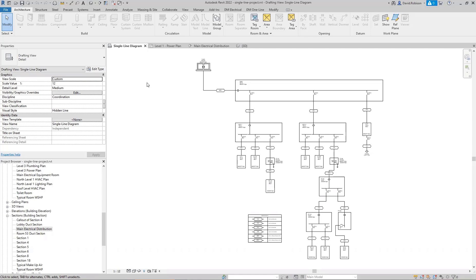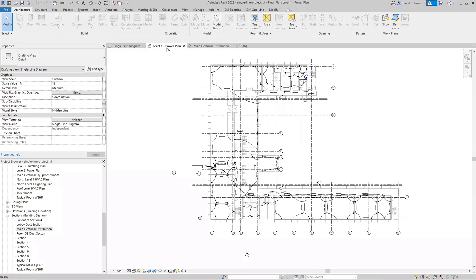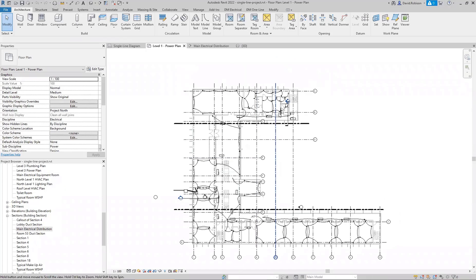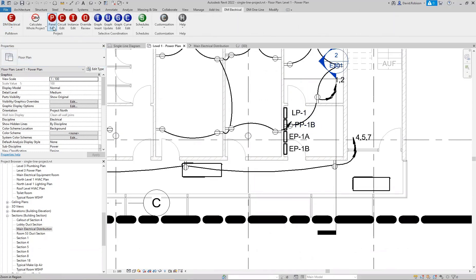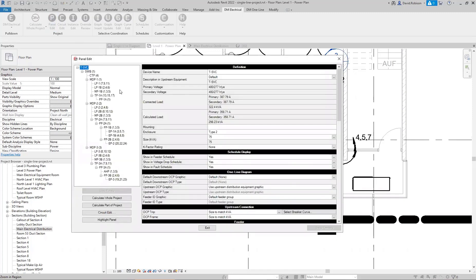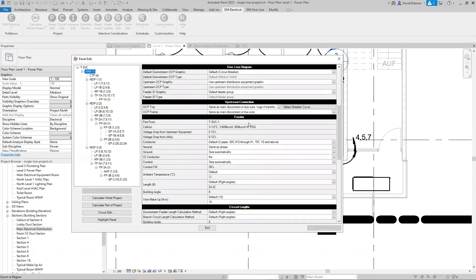Today we are going to be looking at feeder lengths and circuit lengths in Revit and how those calculations work in Design Master Electrical. I'm going to go ahead and go to our power plan. We've got some panels that are inserted in this project, so we'll run the panel edit command. When we do that, it will list all of our panels. If we select a panel and scroll down to the feeder section, there's a whole section at the bottom related to length.